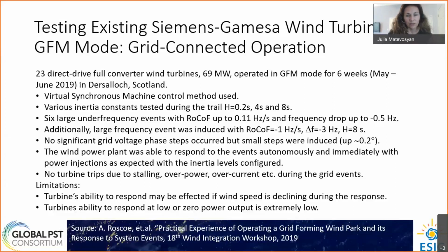There were no significant voltage steps during the trial, and the largest voltage phase step that was encountered was 0.2 degrees. The wind power plant was able to respond autonomously and immediately with power injections as expected, with inertia levels as they were set. There were no turbine trips due to stalling, over power or over current during this trial.